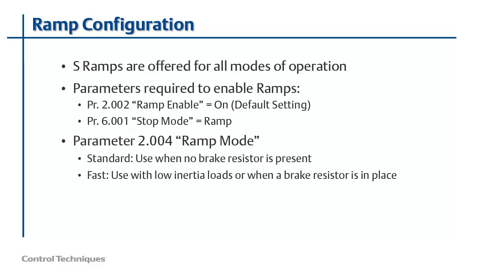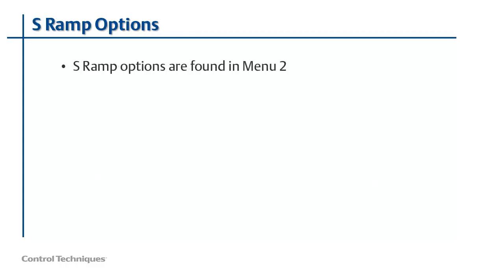Now that the ramps are enabled in the drive, let's have a look at the options for using S ramps. S ramp options are located in menu 2. To enable the S ramp generator, set parameter 2.006 to on.